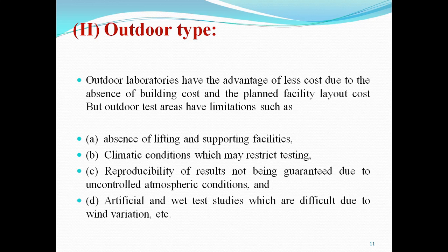for testing, we have to lift the transformer with the help of a chain pulley arrangement, or a crane-type arrangement is required to lift heavy transformers and other equipment. Climate conditions may restrict testing, and reproducibility of tests is not guaranteed due to uncontrolled atmospheric conditions. Artificial rain and wet test studies are also difficult due to wind variations. It means, if you are going to perform a test in the laboratory and you require standard temperature and pressure for the particular test, this is not possible in an outdoor-type laboratory.